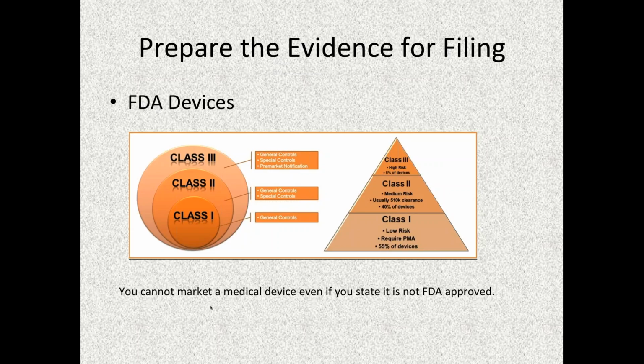And if it falls within the devices, it's under the CDRH, which is the Center for Devices and Radiological Health, and your device will then be classified as either a 1, 2, or a 3. If you see the slide: general controls, special controls, and premarket notification. Class 3 is the most expensive and the most time-consuming. It's basically saying that this device is a life support or life-assisting device, or failure of the device could result in serious harm to the patient or death. Class 2 devices are general controls and special controls, and Class 1 devices are just general controls. Class 2 devices are your 510(k) type devices, and about 40% of the devices that are marketed today fall underneath that class. About 55% fall under Class 1.